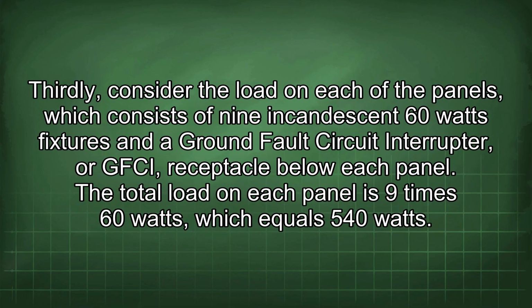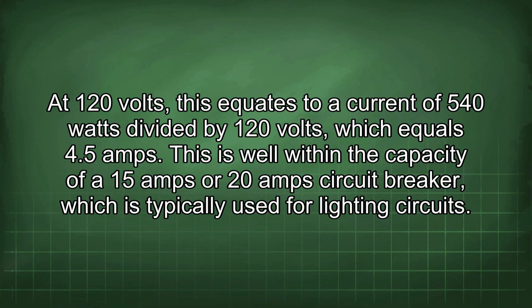Thirdly, consider the load on each of the panels, which consists of 9 incandescent 60 watt fixtures and a ground fault circuit interrupter, or GFCI, receptacle below each panel. The total load on each panel is 9 times 60 watts, which equals 540 watts. At 120 volts, this equates to a current of 540 watts divided by 120 volts, which equals 4.5 amps.